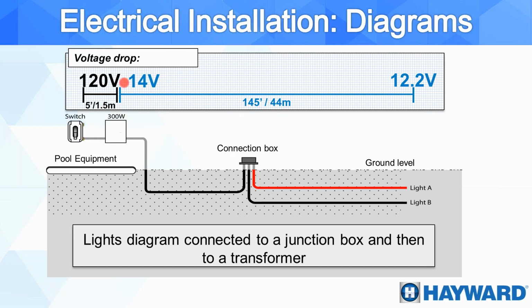Why? Because coming out of the transformer, we are going to get 14 volts. But the longer this wire is, we can see how our voltage is going to drop. In this case, the voltage is coming out at 14 volts, but by the time it gets to the lights, we are actually right at 12.2. Because remember, with low voltage, the longer the wire, the more resistance. So that's why we always recommend coming out of 14 volts in order to mitigate that voltage drop.